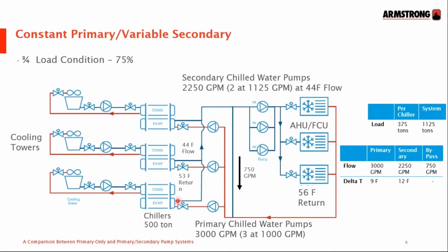But with 3000 going through the primary circuit and 2250 through the secondary, you'll get 750 going through the mixing header here, mixing with the 56-degree water coming back, cooling it down so that it's at 53, going back into the chillers, resulting in a 9-degree delta T across the chiller. So the chiller will be unloaded to 375 ton from its 500 ton capacity. And because they're constant speed chillers, the efficiency will be degraded somewhat.